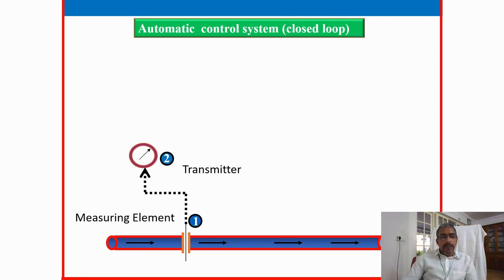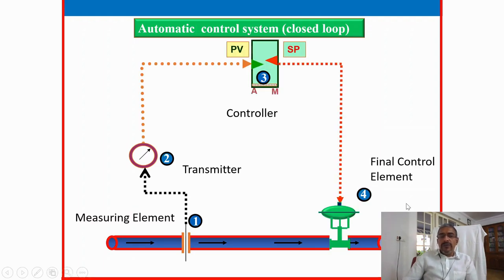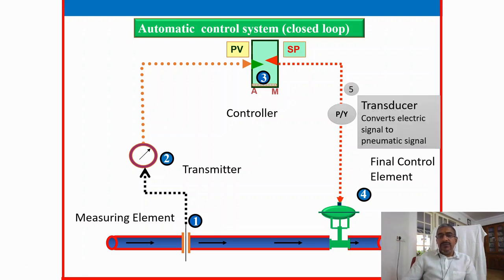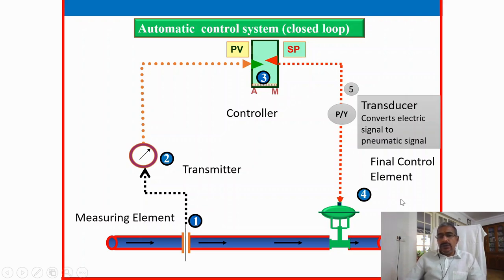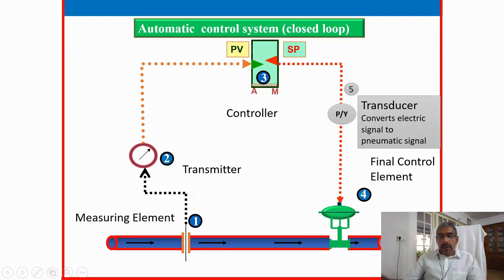The automatic control loop has these components: measuring element, transmitter, controller, final control element — those four we have studied already. One more item added: fifth is PY — the converter or transducer — which converts electrical signal to pneumatic signal. This is added when the controller is an electronic controller. If the controller is a pneumatic controller, we still have to add a transducer because the final control element — the control valve — uses pneumatic signal. Pressurized air is used to lift the opening element of the control valve, so we must use a transducer or converter to convert electric signal to pneumatic signal.